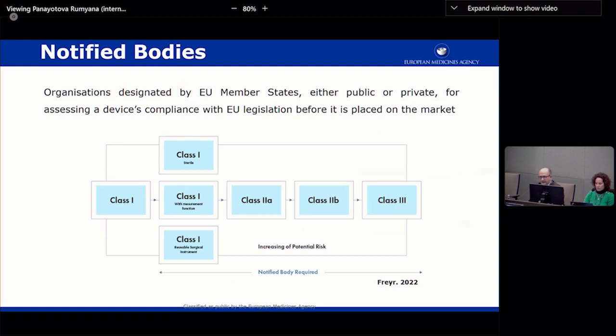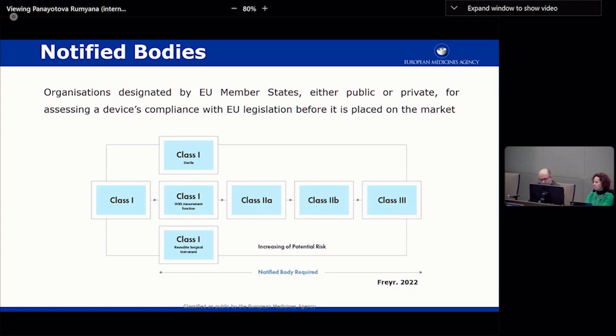It's important to note that, unlike medicines regulation, in medical devices there are third parties involved in the assessment, which are the notified bodies. The notified bodies are designated by the member states and can be either private or public entities. They conduct the compliance assessment with the European regulation before a device can be placed on the market. This assessment applies only to the higher risk products — from Class 2A to 3 and some specific types of Class 1 devices — and even then only for a specific part of the device, such as the sterilization process for a Class 1 sterilized device.